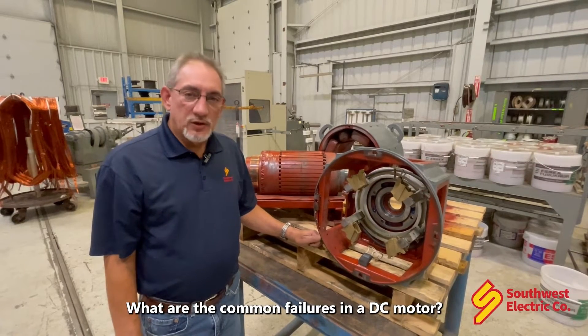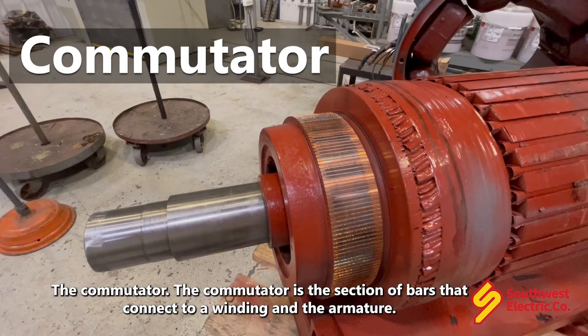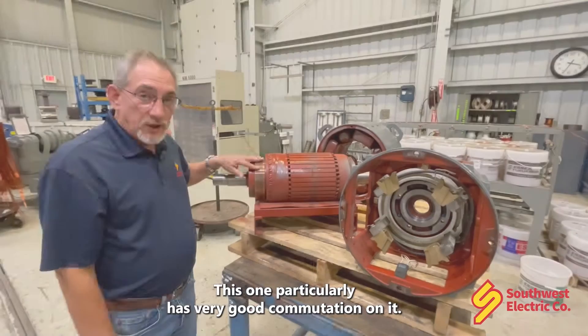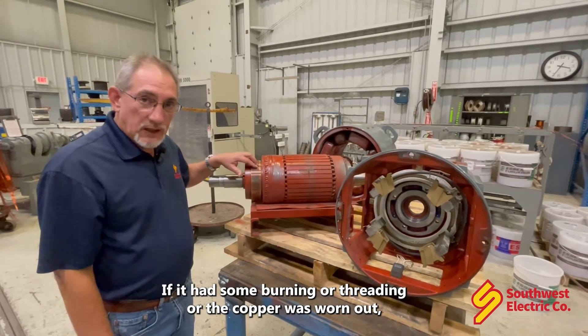What are the common failures in a DC motor? The first thing we're going to look at when we get a motor in for repair is the commutator. The commutator is a section of bars that connect to a winding in the armature. This one particularly has very good commutation on it. If it had some burning or threading, or the copper was worn out, that would indicate a problem.